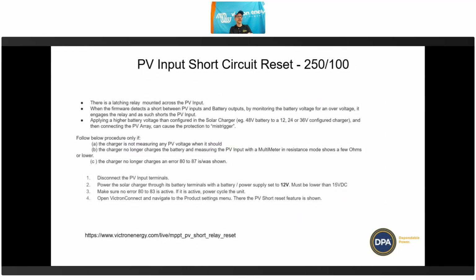This usually happens during commissioning when somebody has not set the battery voltage correctly, and they've, say, turned on the PV first, and then it thinks it's a 12-volt battery for whatever reason, and then you connect a 48-volt battery and it goes, whoa, and it will short out those input terminals.